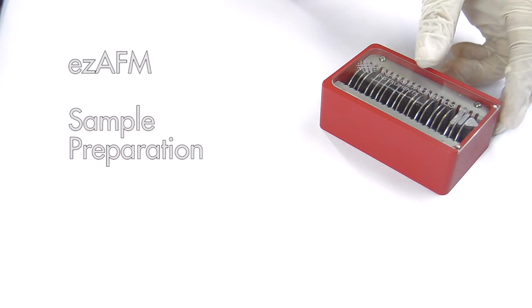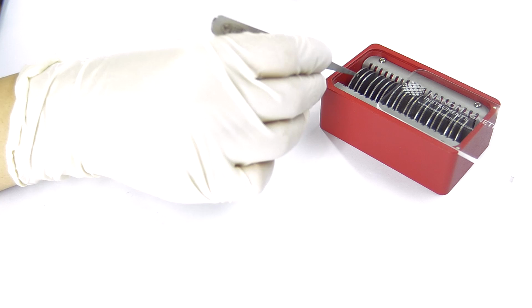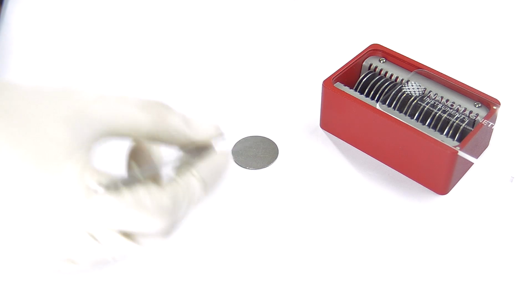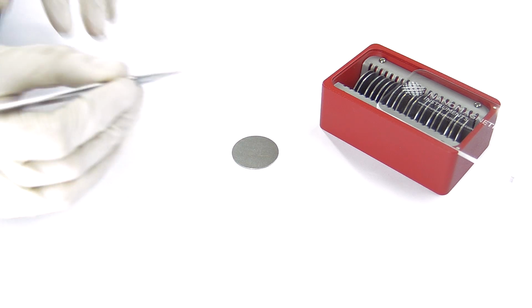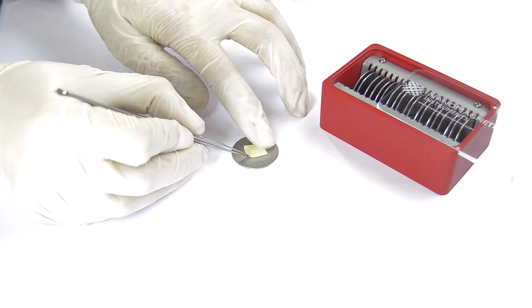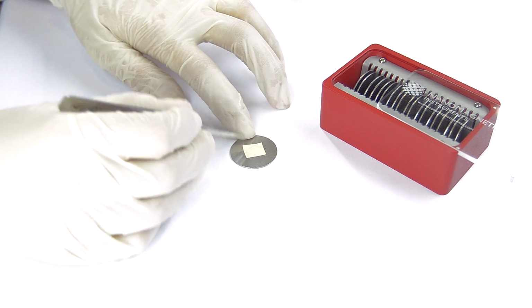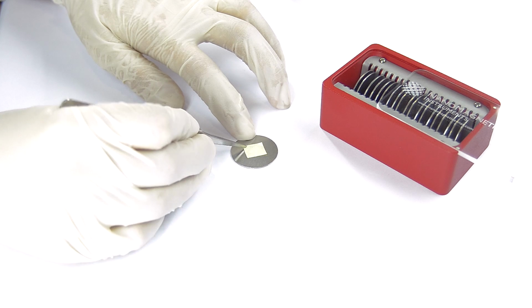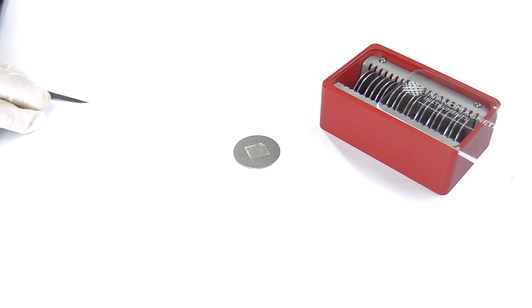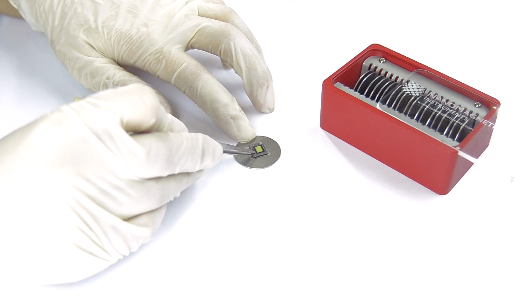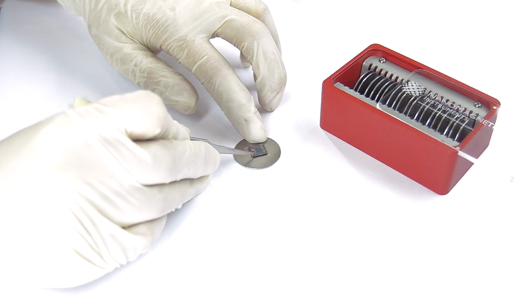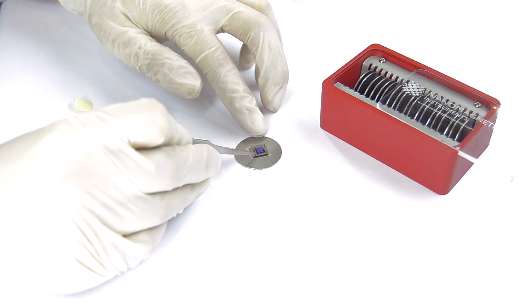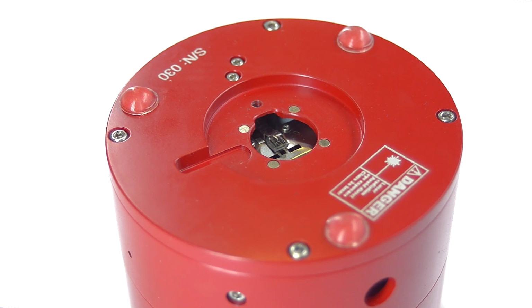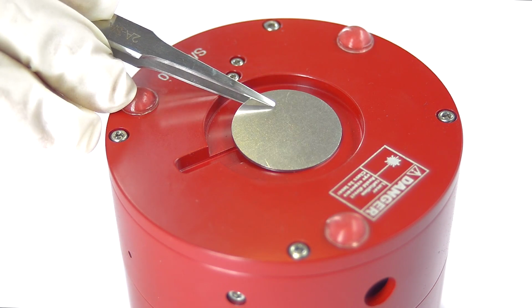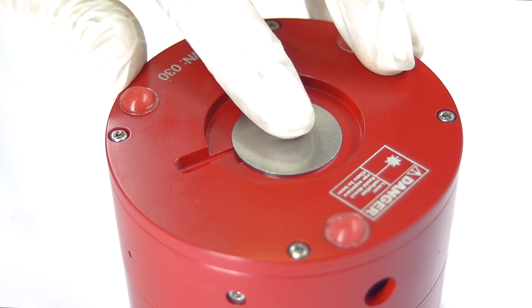Open your sample box and take an empty sample holder. Cut a piece of double-sided tape and affix to the sample holder. Remove the protective paper and affix your sample on the tape. Try to place your sample as flat as possible. Attach the sample holder to the scan head and manually center the sample.